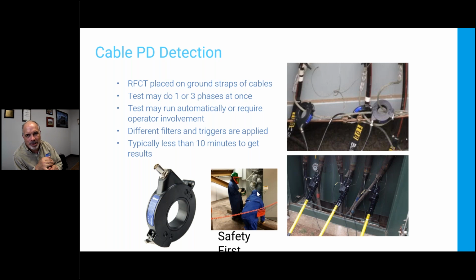The big push now is permanent RFCTs that come out to test points, or they use the HFCT on the hot stick, or sometimes on riser poles the grounds will come down low enough where you can grab it. But not much is done that way. You can also shut off power, connect everything, re-energize, but it takes time.